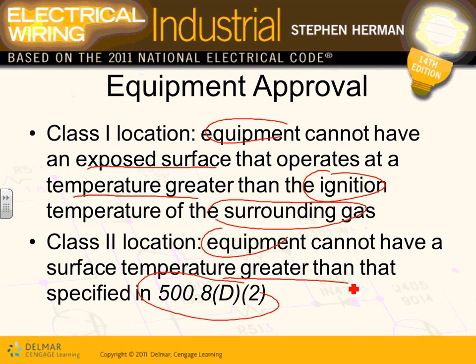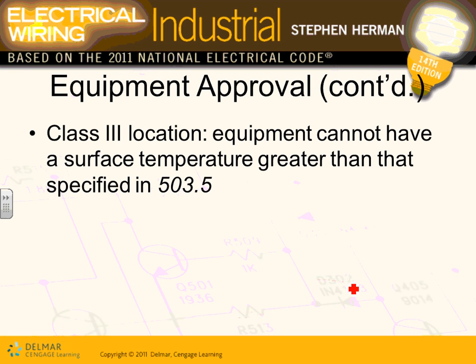So it's explosion proof. The whole idea is not to ignite the dust, the fiber, or the gas. That's your area. In a class 3 location, the same thing, guys. The surface temperature of the equipment cannot be greater than what's listed in these tables, which will give you a temperature limitation. Same thing, fiber. You have fiber, paper mills. You have all this paper in paper mills all over. Do you want the temperature to get hot enough to ignite the paper mill and get it all in a big explosion?